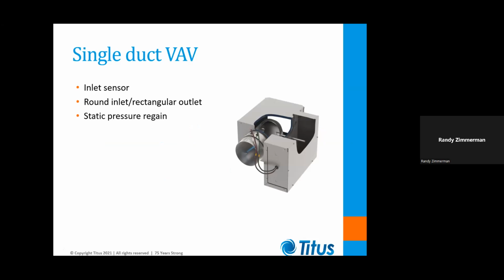And of course, the most basic terminal unit would be your single duct VAV box. If you look at this cutaway picture here, you can see the structure of the unit. It's got the round inlet with a flow sensor in it so that the control system, which is hopefully going to be pressure independent, can actually monitor the inlet velocity of the terminal unit and then allow the controller to automatically adjust the damper position to deliver the desired CFM, and automatically correct for changes in inlet pressure.